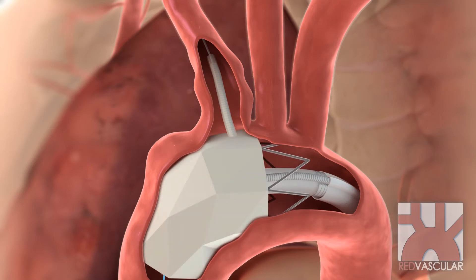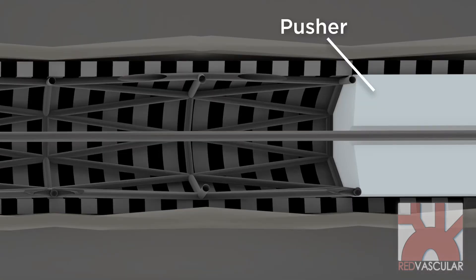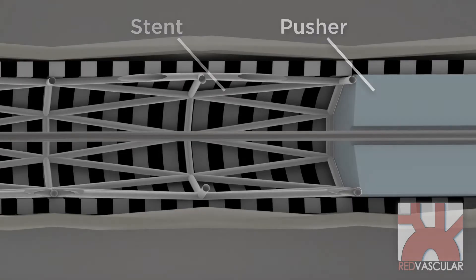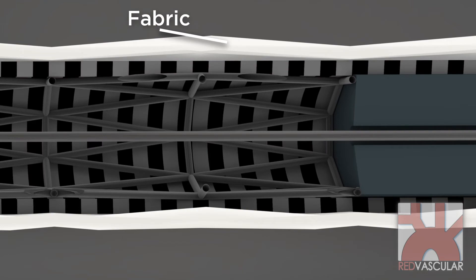Let's look at the branch delivery mechanism, which permits unsheathing of the branch graft from the same access site as for the main graft. The pusher stabilizes the wire stent during delivery. The branch sheath lies between the stent and the outer fabric.